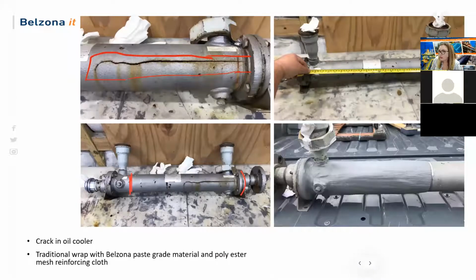Here's an example on an oil cooler. You can see the crack was pretty significant, and the asset owner wasn't able to weld this or do any other application due to the oil being too dangerous to weld with it built up. They needed this back and weren't able to get another piece of equipment for weeks. We were able to return it with a Belzona paste grade composite wrap around it in 24 hours.